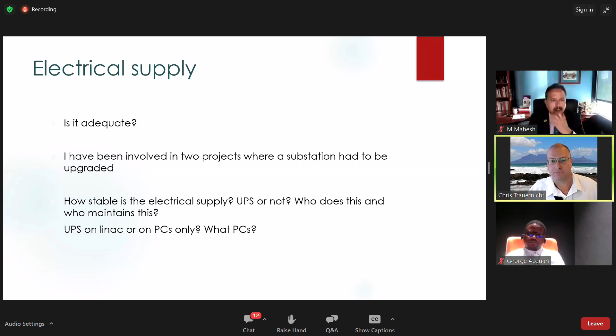So we specify that we can finish treating the patient on the bed. But who does this? The engineering, or is it the vendor? And who maintains it? Who will replace the batteries after 3 years? Is it the hospital? Because that will be a very nice chunk of change that they will have to come up with. Or does it become part of the specifications? Do you want the UPS on the LINAC or only on the PCs? And if the PCs, which PCs? This is just something you should think about.